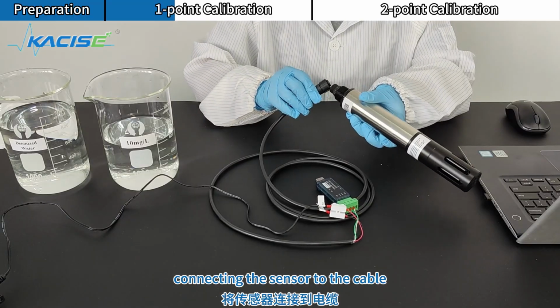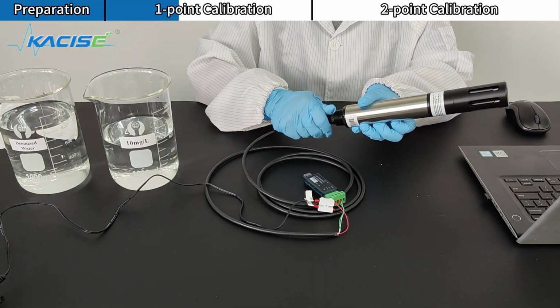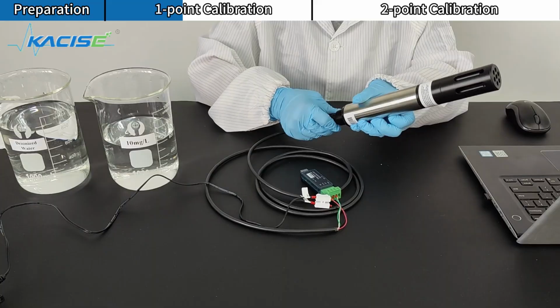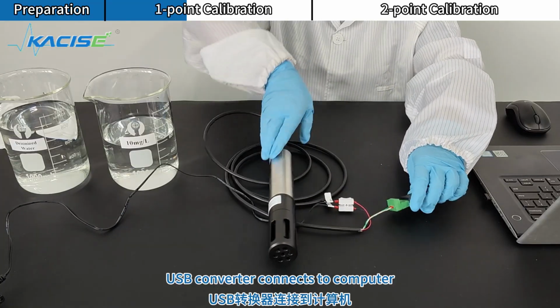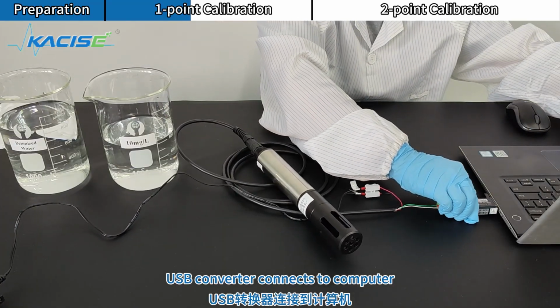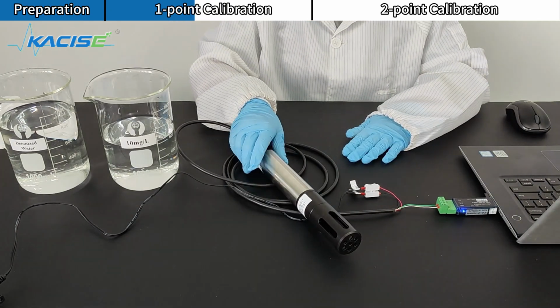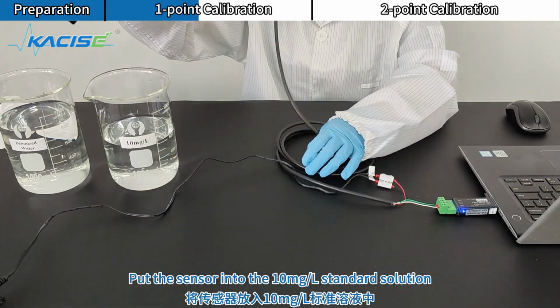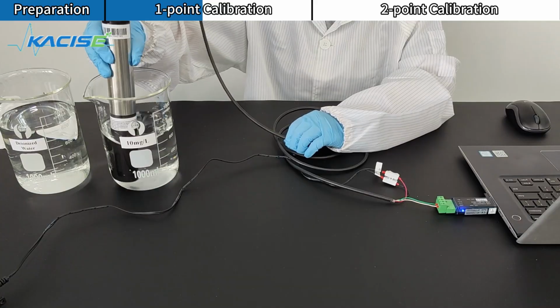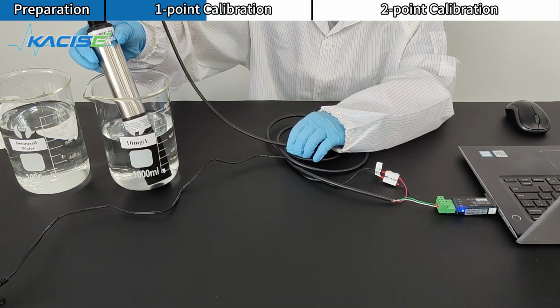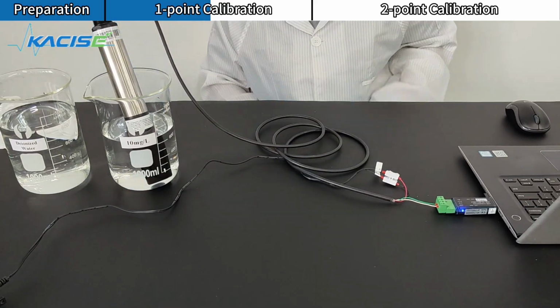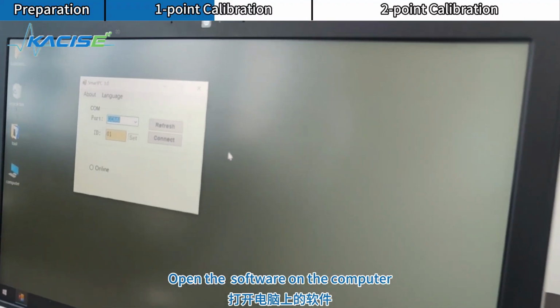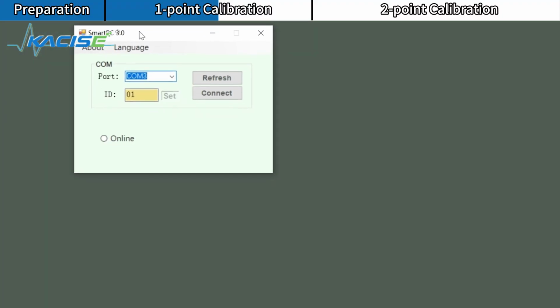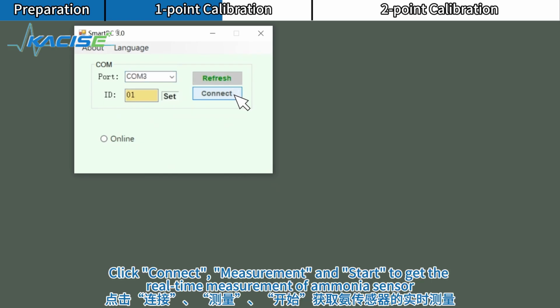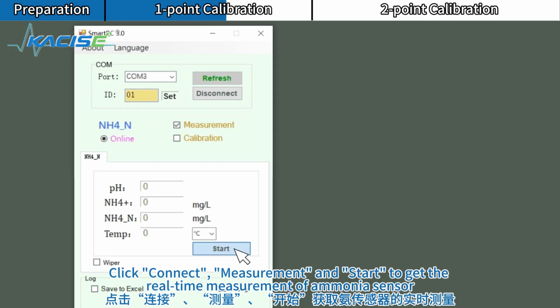Connecting the sensor to the cable. USB converter connects to computer. Put the sensor into the 10 mg/L standard solution. Open the software on the computer. Click Connect, Measurement, and Start to get the real-time measurement of the ammonia sensor.